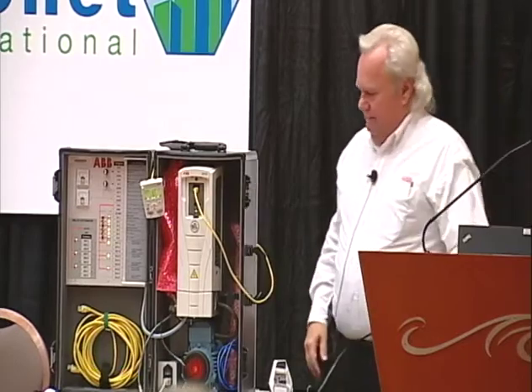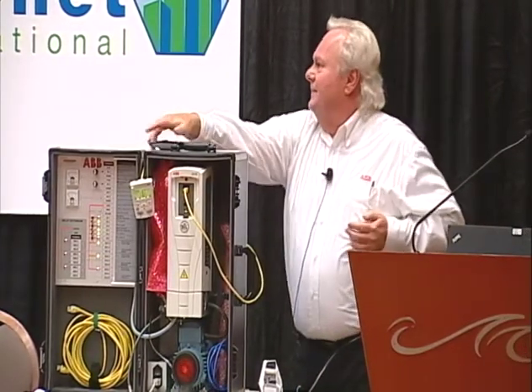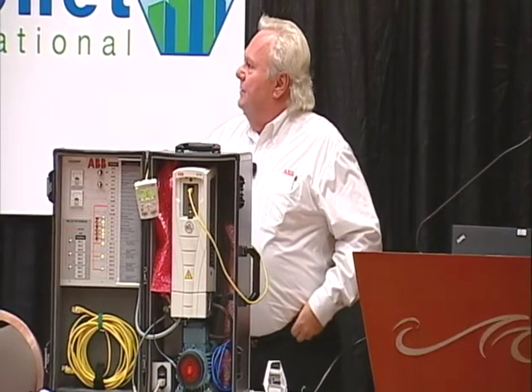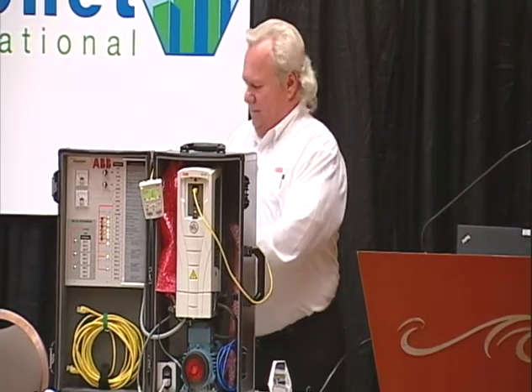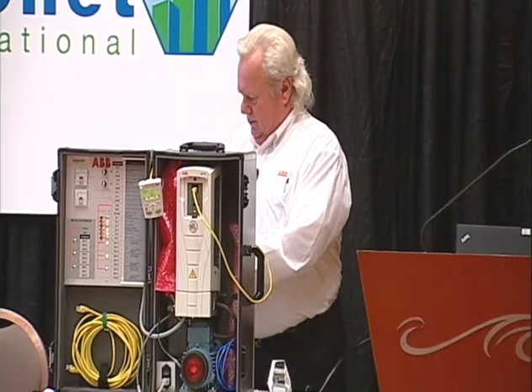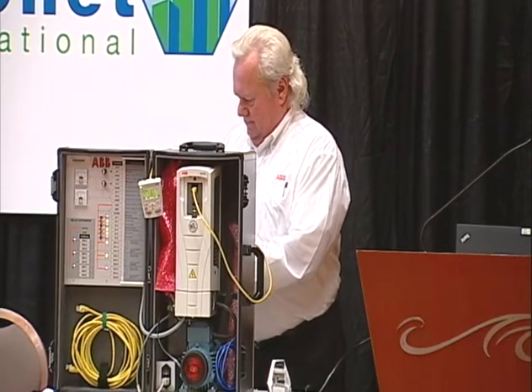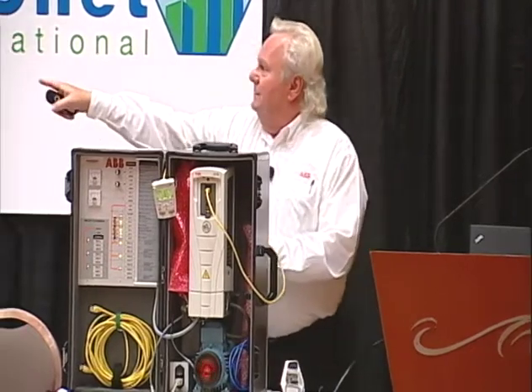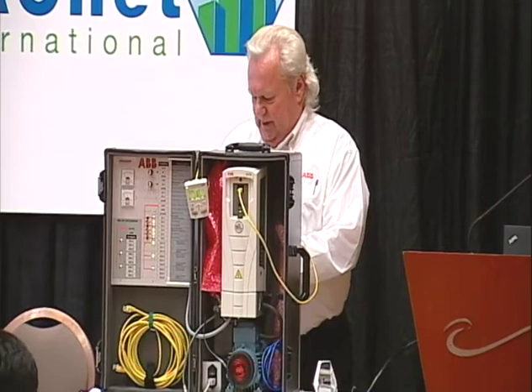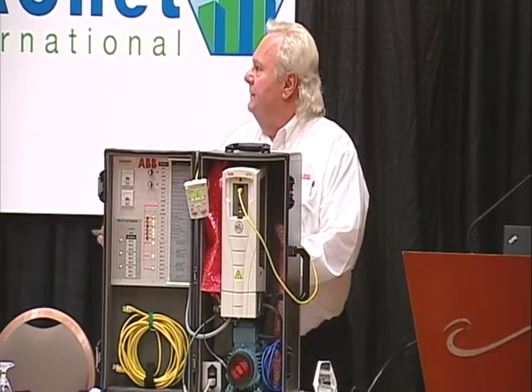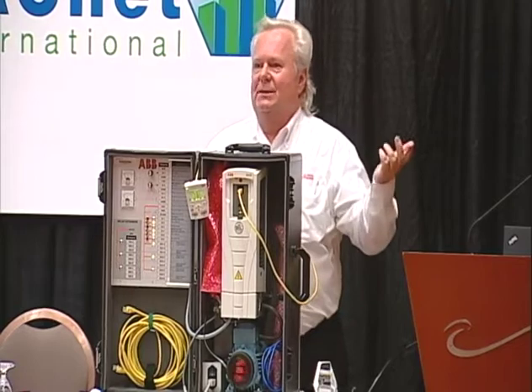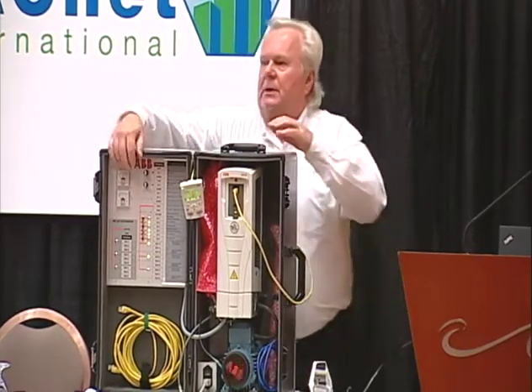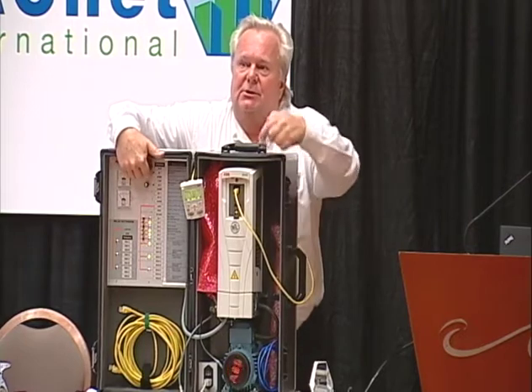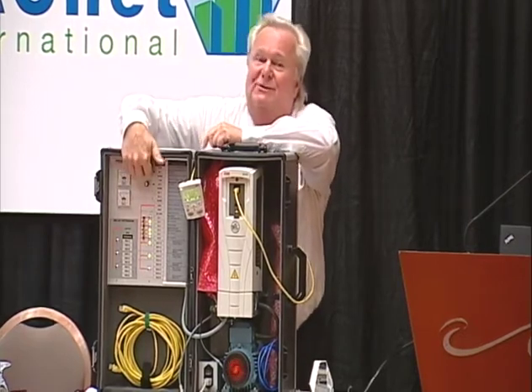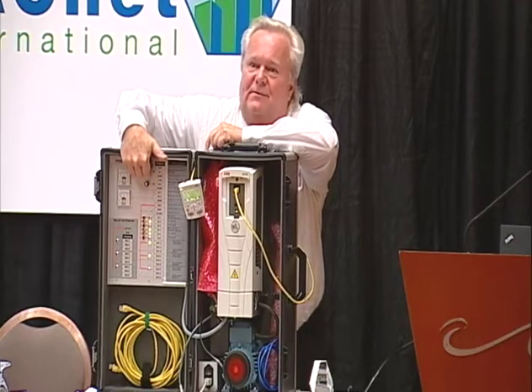So now, if I find my pointer, there it is. You can see the computer is asking the drive questions, but the drive's not responding. And neither is my pointer. You see the line there between the EMS box, which stands for Energy Management System, and the VFD? It's asking questions, the VFD is not answering because the wire's cut. But notice, if my pressure goes down, now the graphic's not gonna change, but you'll see it change here. If pressure goes down, the fan still speeds up. Pressure goes up, the fan still slows down.